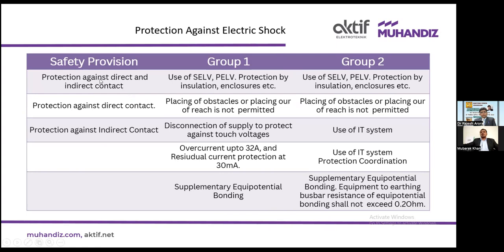There are various safety aspects which are common in designs for preventing electric shock. Okay. First is prevention against direct and indirect contact. It can be done using SELV, PELV. It is allowed in Group 1 as well as Group 2 locations. Like using extra low voltage to prevent electric shock is allowed in Group 1 as well as Group 2 locations. Now, protection against direct contact. Okay. Placing of obstacles or placing out of reach is not permitted. And we should have insulation on top of the live conductors, or enclosures are required.